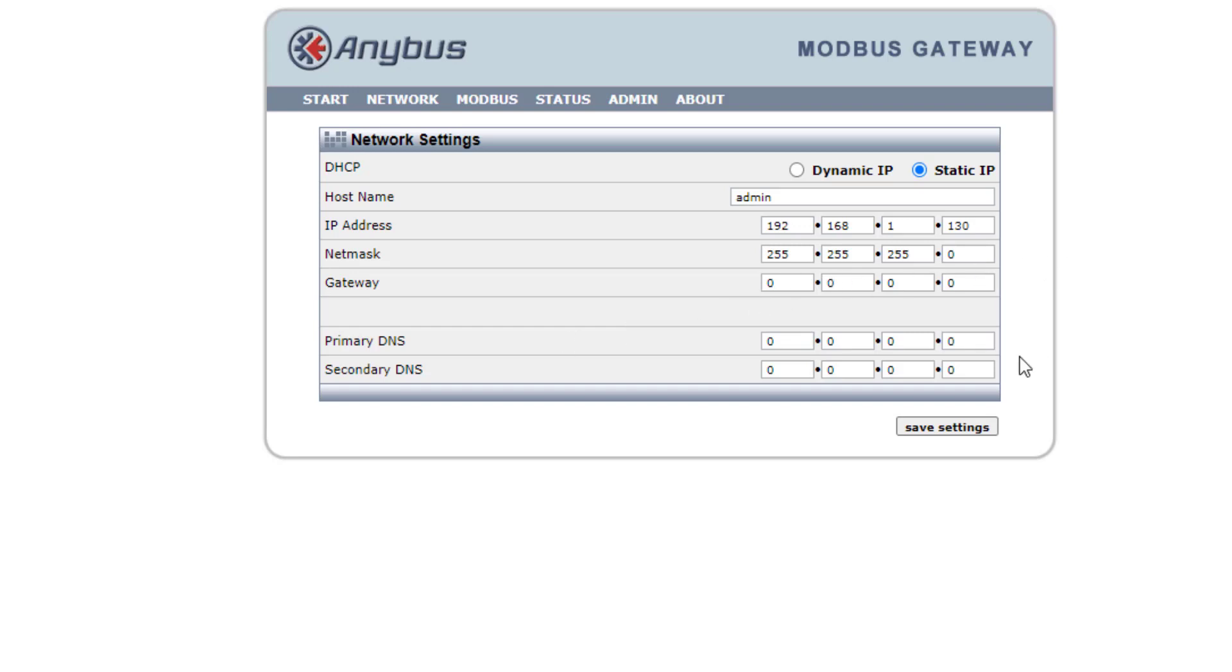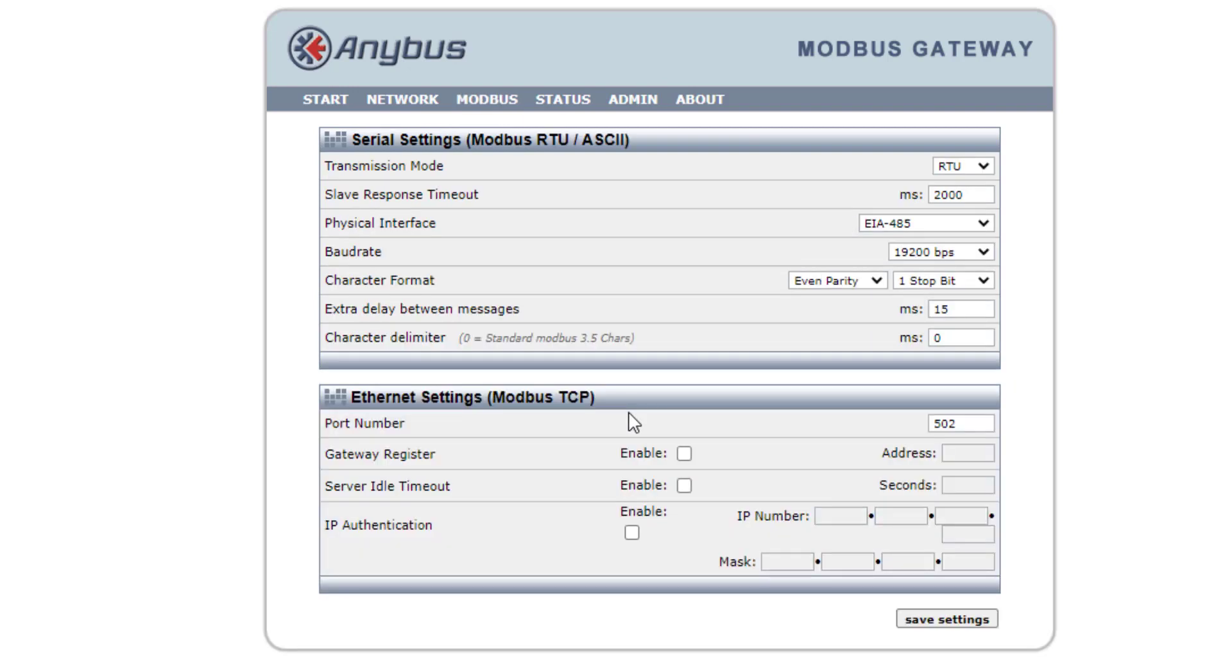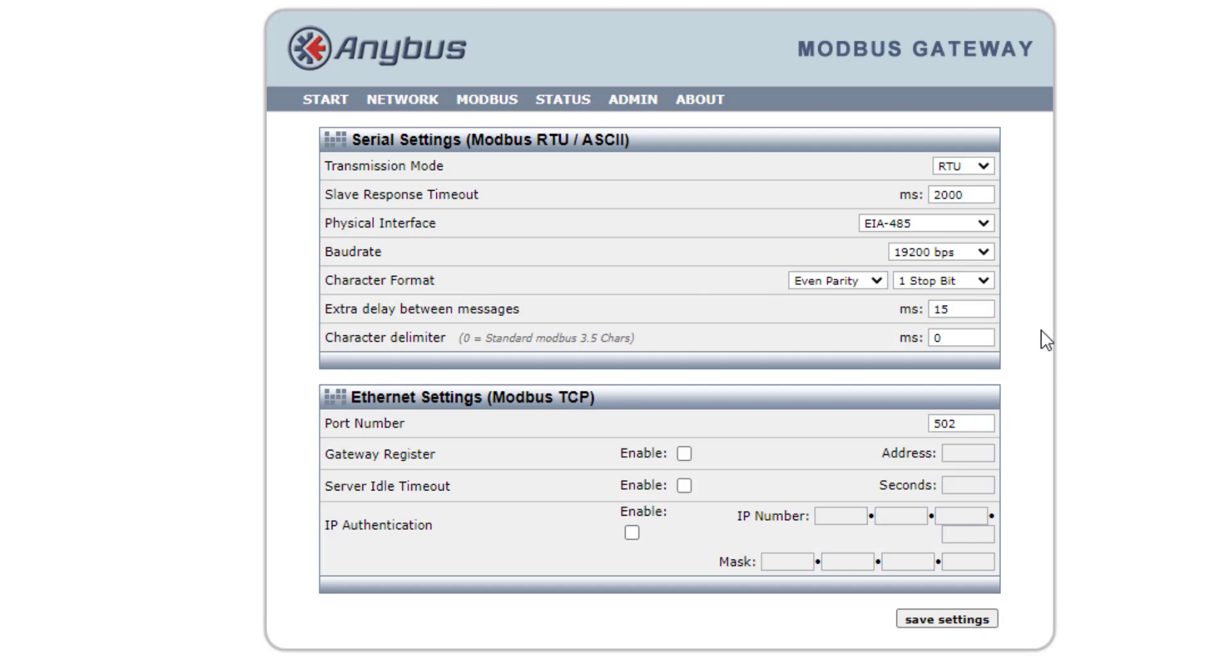So the serial converter that's sat on the PDM PC needs to be sat on the same domain as the converter. Save your settings there. Then we go to the Modbus 485 side of the device. You can see here Physical Connection 485. We're going to be connecting this to a Siemens Sitrans FC410. The default baud rate for that device is 19,200, parity is even, stop bits is 1. So I put that in so it's less changes that you have to do to the flow meter.